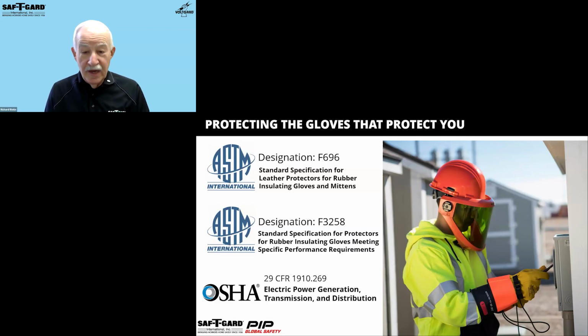The OSHA 269 standard that I referred to earlier, that's 29 CFR 1910-269, requires that rubber insulating gloves with protector gloves must be worn by qualified employees within that minimum approach distance to exposed energized conductors.